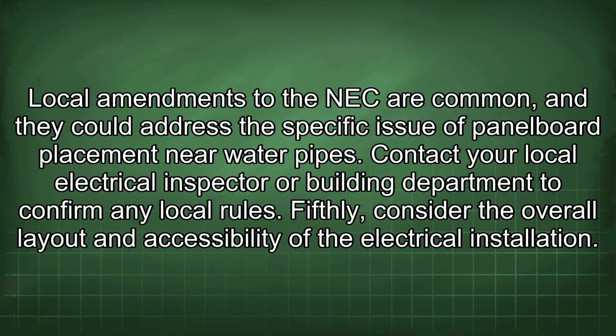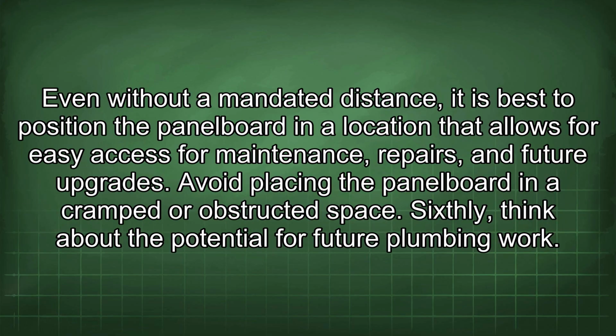Local amendments to the NEC are common, and they could address the specific issue of panelboard placement near water pipes. Contact your local electrical inspector or building department to confirm any local rules. Fifthly, consider the overall layout and accessibility of the electrical installation. Even without a mandated distance, it is best to position the panelboard in a location that allows for easy access for maintenance, repairs, and future upgrades. Avoid placing the panelboard in a cramped or obstructed space.